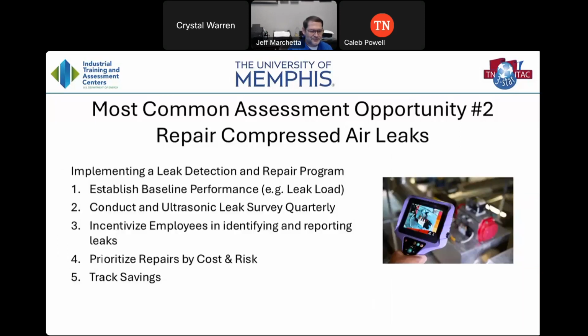Next slide. So what do we recommend? We recommend a leak detection and repair program. What is the implementation? Well, if you look over in that picture, you'll see that little purple handheld device. That is what we use. That costs roughly $7,000. Just purchased one last year as a replacement. You can get an ultrasonic leak detector for as little as $1,500, or something a little bit more expensive like this for $7,000.